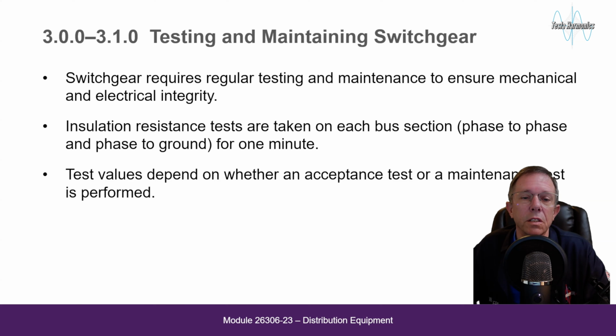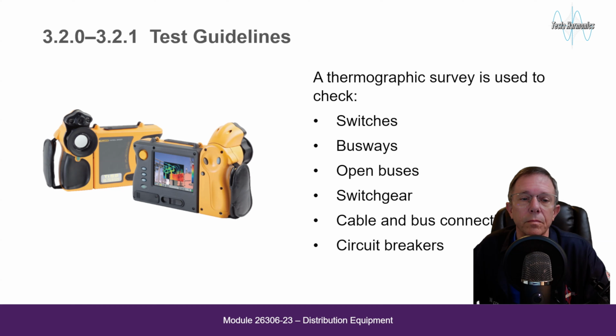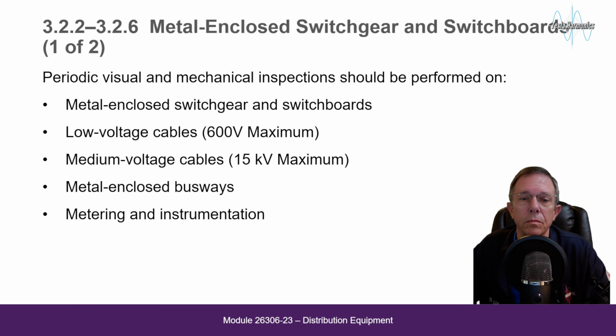Insulation resistance tests are taken on each bus section, phase to phase and phase to ground for 1 minute. Test values depend on whether an acceptance test or a maintenance test is performed. Test guidelines. A thermographic survey is used to check switches, busways, open buses, switchgear, cable and bus connections, and circuit breakers. Metal enclosed switchgears and switchboards.